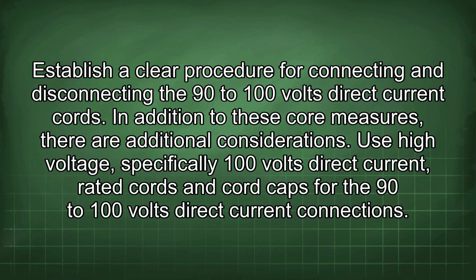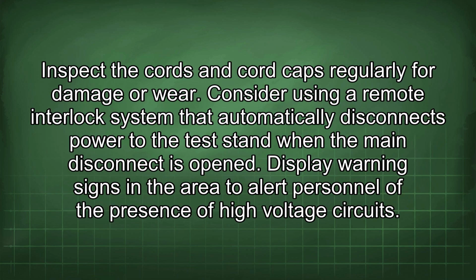In addition to these core measures, there are additional considerations. Use high voltage, specifically 100 volts direct current, rated cords and cord caps for the 90 to 100 volts direct current connections. Inspect the cords and cord caps regularly for damage or wear. Consider using a remote interlock system that automatically disconnects power to the test stand when the main disconnect is opened. Display warning signs in the area to alert personnel of the presence of high voltage circuits.